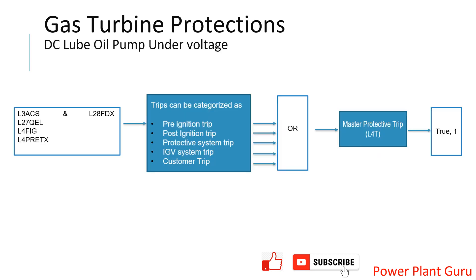The GCV L3ACS is the GCV SRV related command versus feedback error trip, which we covered in the last video. Today's topic — L27QEL — is related to DC LOP, that is EOP. Sometimes people call it EOP only. This is a check where the gas turbine control system checks whether your EOP is available or not before starting the machine.